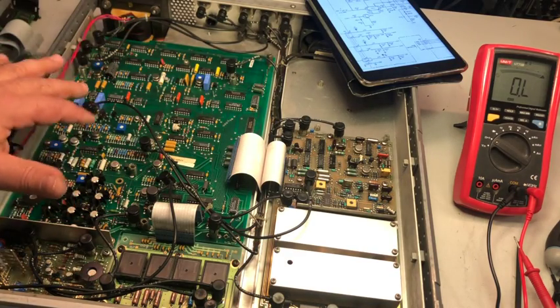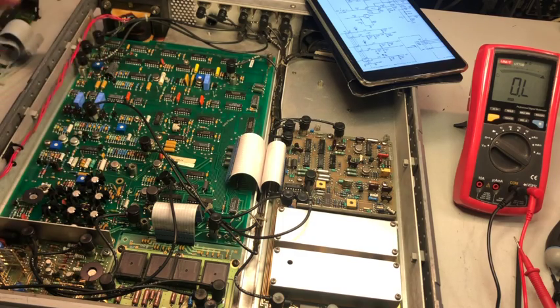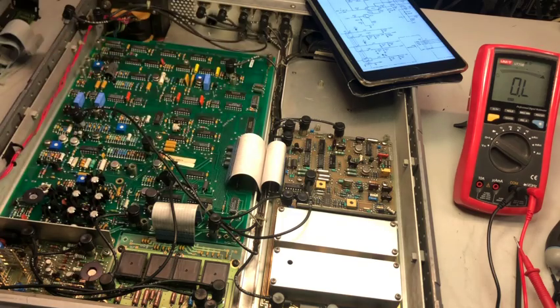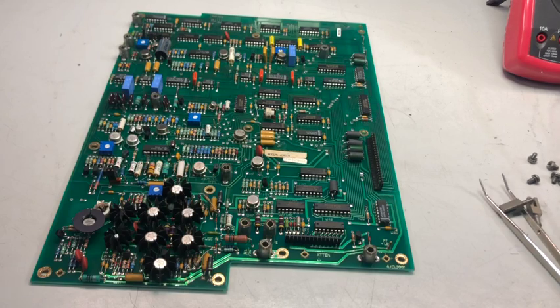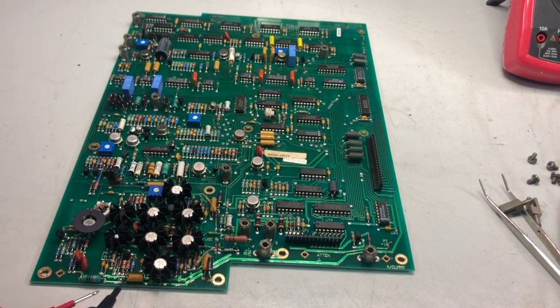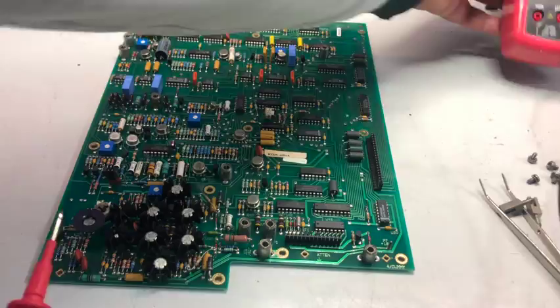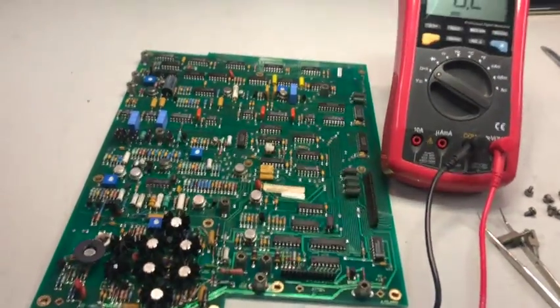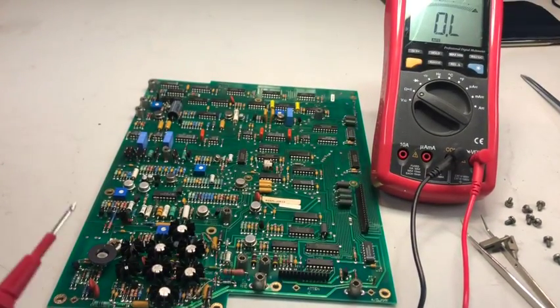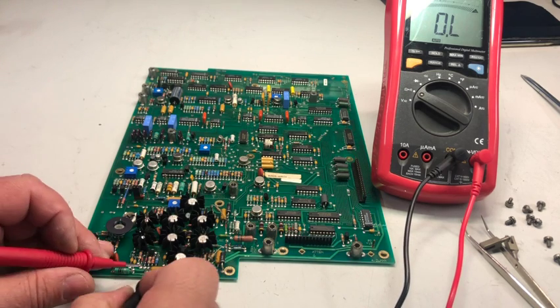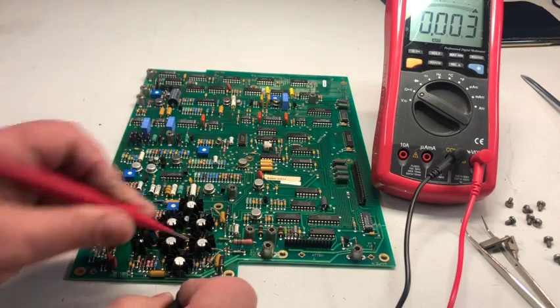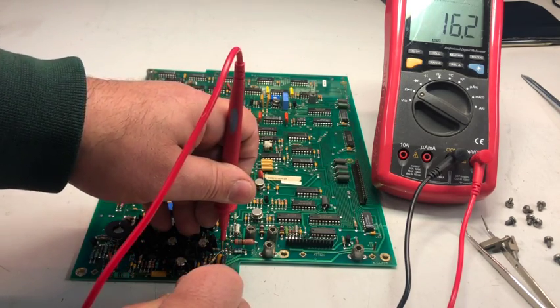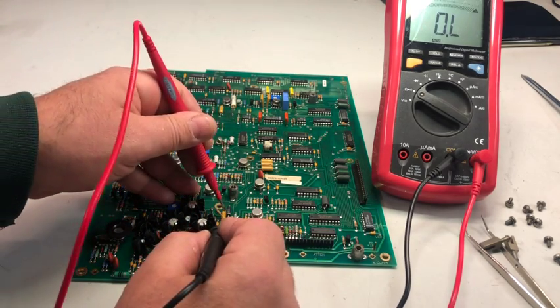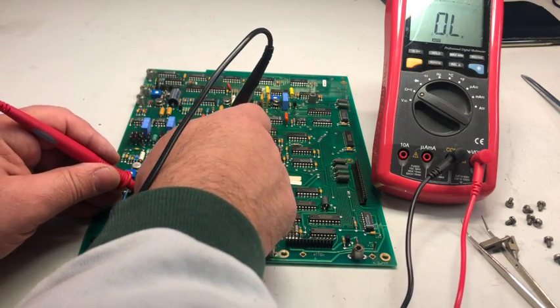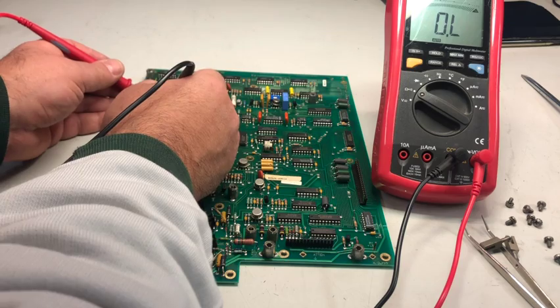Well, to troubleshoot this short circuit requires the board removal, so I will remove it from the instrument and check on the bench. The first thing that I have noted are this kind of capacitor, which I believe are tantalum capacitors, and just poking around and measuring the closest, bang, short. But also this one, it's 16 ohms, which is a bit low. The other seems in an acceptable range of measurements.